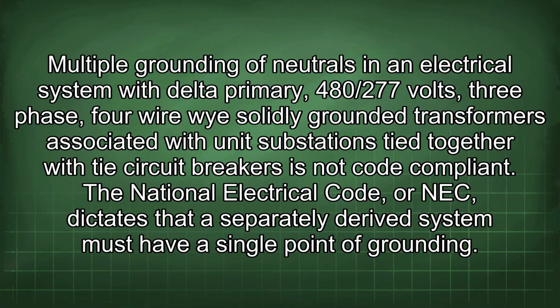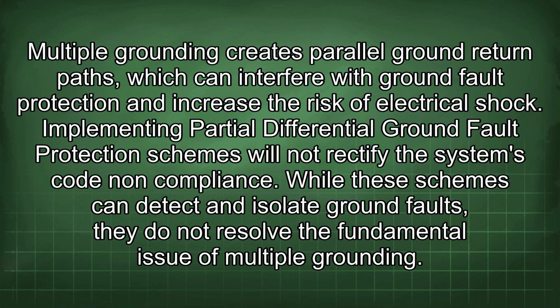Multiple grounding of neutrals in an electrical system with delta primary. 480/277 volts, three-phase, 4-wire Y solidly grounded transformers associated with unit substations tied together with tie circuit breakers is not code compliant. The National Electrical Code, or NEC, dictates that a separately derived system must have a single point of grounding. Multiple grounding creates parallel ground return paths which can interfere with ground fault protection and increase the risk of electrical shock.